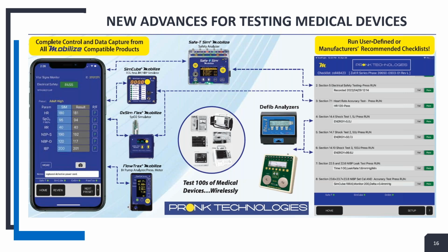Oh, that's the tolerance. So we want to set the current to 140, and the tolerance is plus or minus 7. So defib set for that pacer mode, we go ahead and hit run, and again, it'll sample it and give us the results. But what's helpful is that you've got the setting on there, pass-fail tolerance, and in that gray box below, you'll see your result.